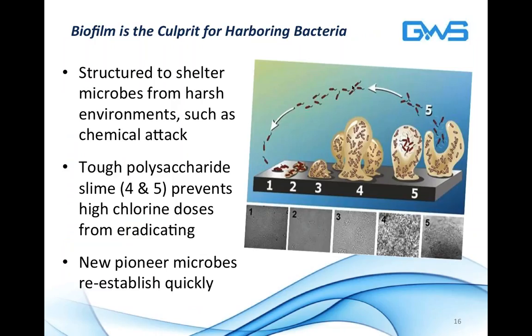The reason is that biofilm harbors bacteria, including Legionella, sheltering microbes from chemical attack and other aquatic attack in the system. It's a tough polysaccharide slime that prevents even high chlorine doses from eradicating it. As the system progresses, new pioneer bacteria emerge from the mature biofilm and establish new colonies elsewhere, making mature biofilm self-regenerating in cooling water.